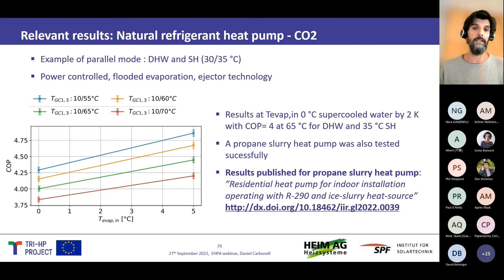If we look at the normal 10-55, so 10 is the inlet of the cold water, and 55 is what we provide as domestic hot water, we can see that when the evaporator temperature on the water side, T evap in, meaning water inlet, is 5 degrees, the COP is above 4.7, which is very good. Also very interesting, we can see conditions at 0 degrees. In these conditions, water was entering at 0 degrees and leaving the supercooler, the evaporator, at -2 degrees. It was stable, no freezing, and we can achieve very high performance there. For 10-55 degrees domestic hot water, the COP was above 4.2. Also you can see in this slide a link to a publication we did for a propane heat pump. We also did the same for a propane heat pump, and we tested it, but I cannot show it here. You can go to this publication.